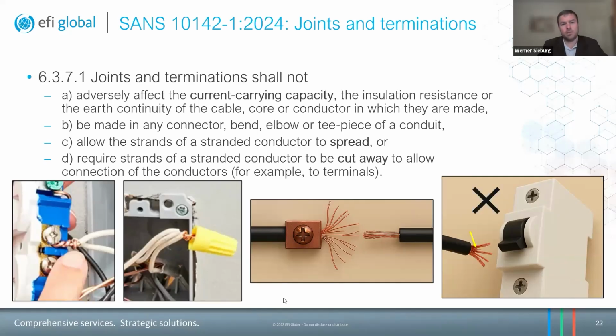So the bottom two are basically what I find quite often in electrical installations, where two cables or two conductors are twisted around each other. The premise of the person making this joint is that as long as I make the surface area between the two conductors big enough, and as long as I give it enough twists, surely the contact area will be sufficient.